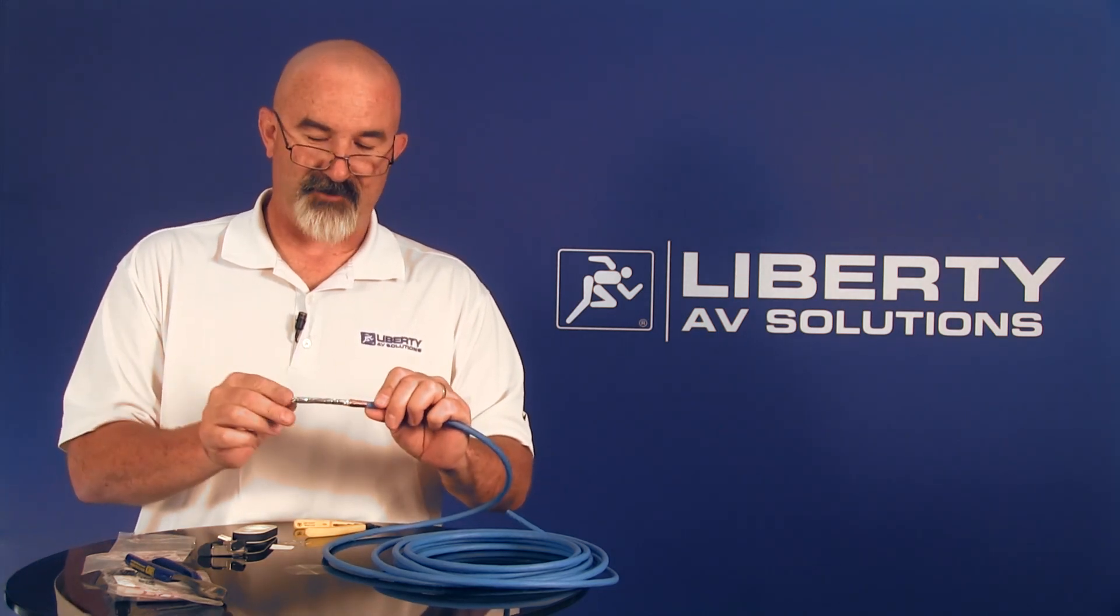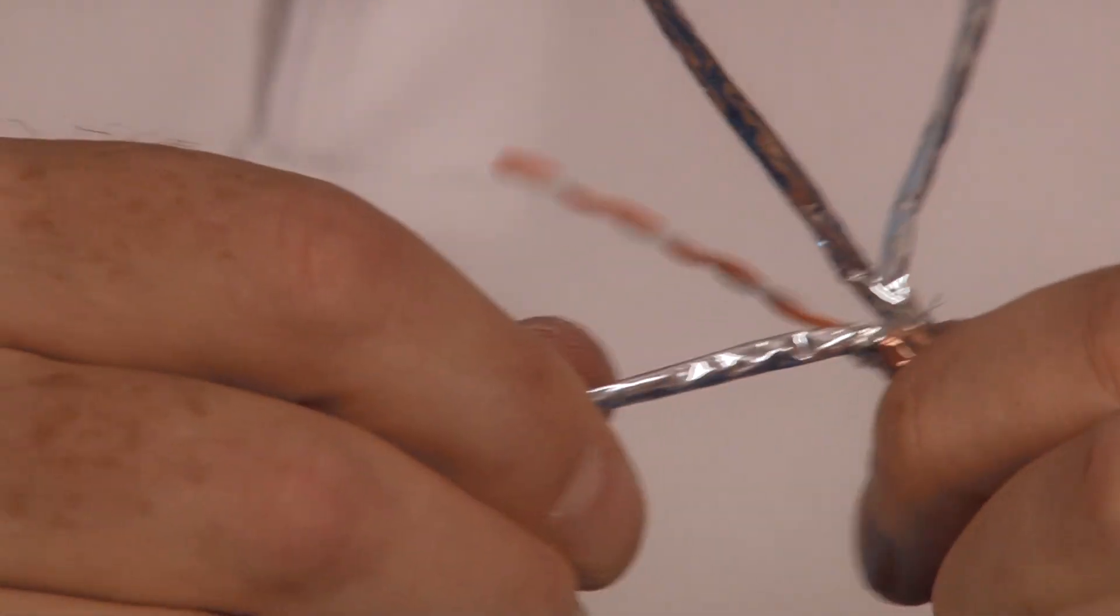Next step is going to be to strip the foil off each of the individual pairs. So I'll separate these out. Each foil has a seam on it and what I want to do is find the seam, follow it all the way down to the edge of the jacket and give it a little nip. Then I can just twist the foil shield right off. I do not want to untwist the wires at this point.